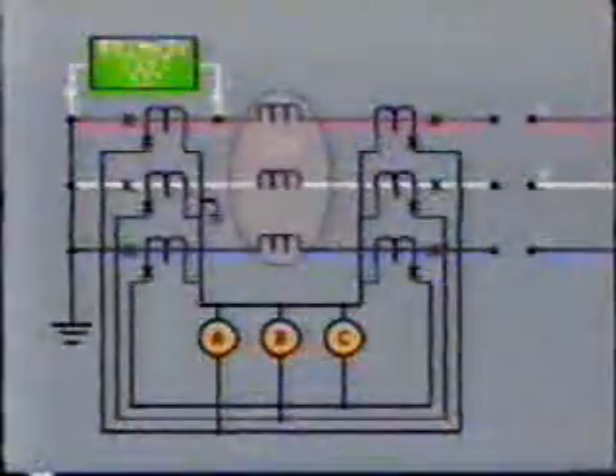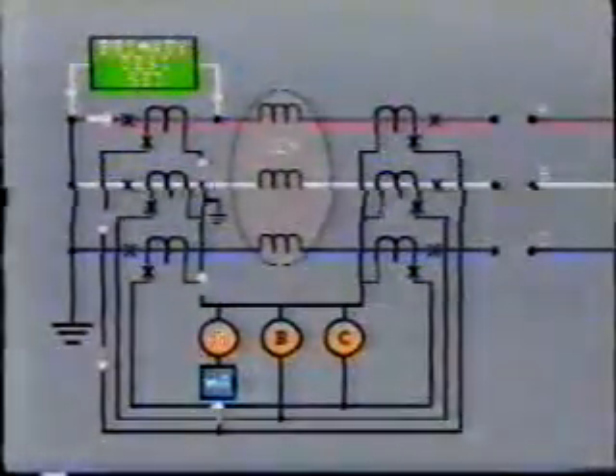This arrangement shows generator differential protection. The test set is connected like this. Primary current is passed through one CT only, and the value increased until the corresponding relay operates. This value of test current indicates the value of fault current required in the primary to operate the relay. The test is repeated for each separate phase.